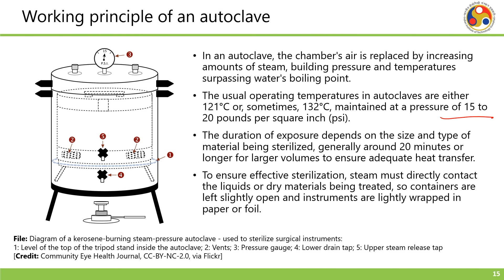Quality assurance in autoclaving. To verify successful sterilization, internal indicators of various types are autoclaved alongside the material. Heat sensitive autoclave tape is a common type, turning black upon reaching the correct temperature, but it does not indicate exposure duration, so it cannot confirm sterility. Another indicator, the biological indicator spore test, uses spores of heat resistant bacteria like Geobacillus stearothermophilus to confirm endospore destruction. After autoclaving, the spores are incubated to ensure none remain viable. Monitoring subsequent bacterial growth helps detect any surviving spores, ensuring complete sterilization.